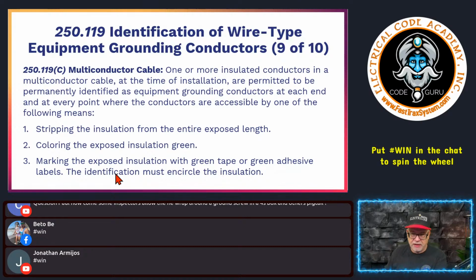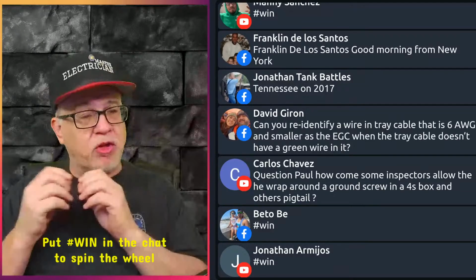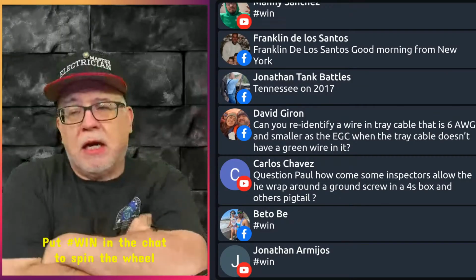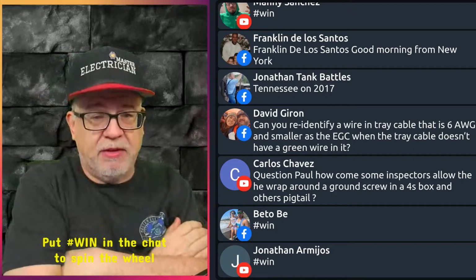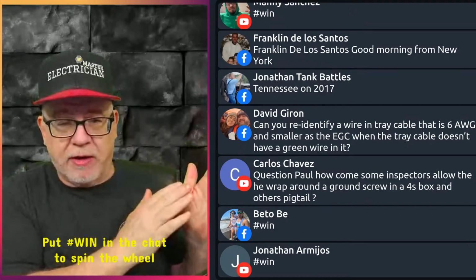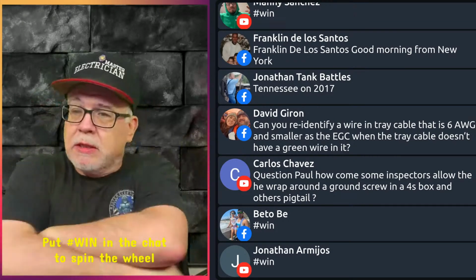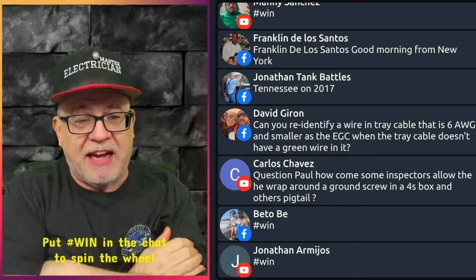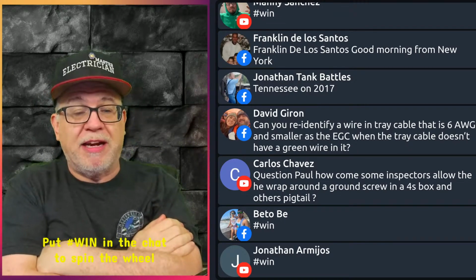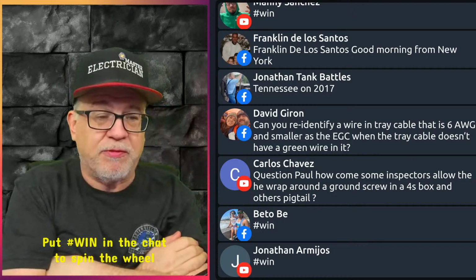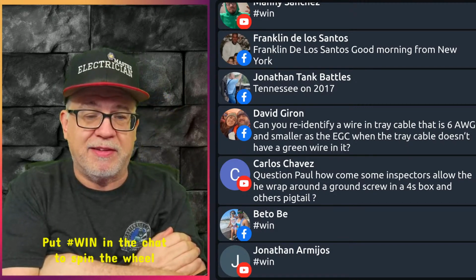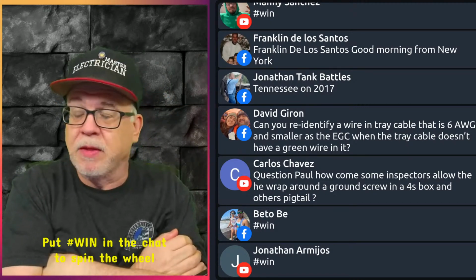Must encircle it, okay? So a lot of people, if they're using a cable, will just strip off the insulation. I guard against this, and I'm going to tell you why. If it's in a cable assembly and you want to use one of the conductors as an equipment ground, it doesn't apply to 4 and larger because that's other applications. This is in a multi-conductor cable. And it is not size specific, by the way, except the equipment ground has to be properly sized based on 250.122, whatever the overcurrent protective device is. That's a given.